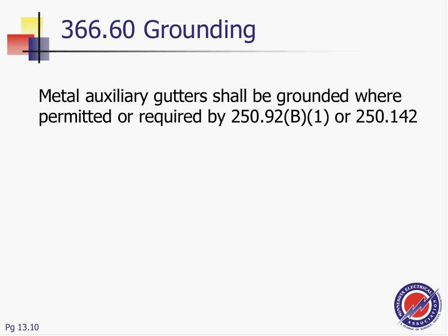Okay, basically taps, identify them. Gutter grounded: if you have a metallic gutter, it shall be grounded. The metallic auxiliary gutter shall be connected to an equipment grounding conductor, to an equipment bonding jumper, or to a grounded conductor. So if you have a gutter, you have to tie it to an equipment grounding conductor, or a bonding jumper if it's not.